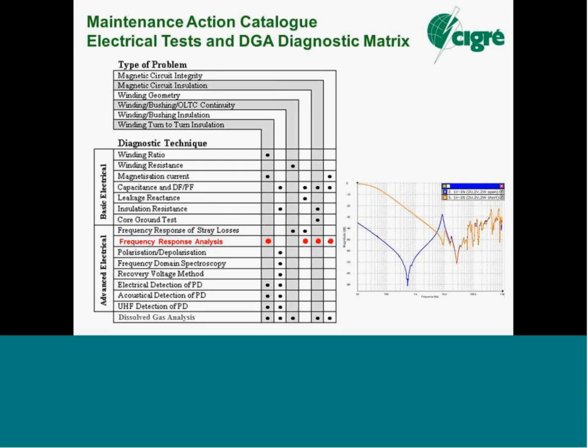In part of the frequency spectrum, say 1 kilohertz upward, you'll probably see changes in that band for winding to winding geometry changes. In other words, uplift, distortion, collapse. Or we have within-the-winding changes, in other words, buckling, torsion of the structure, which change the series capacitance, the shunt capacitance, but more importantly, the series capacitance of the winding. You can see that in the tens of kilohertz through to 1 megahertz frequencies.